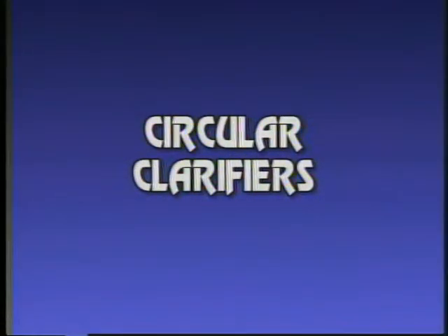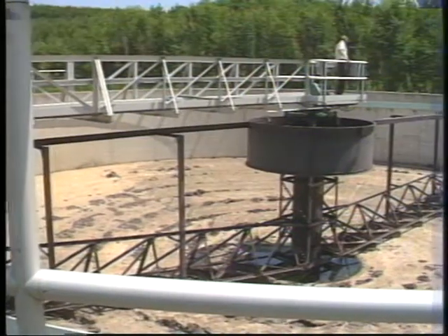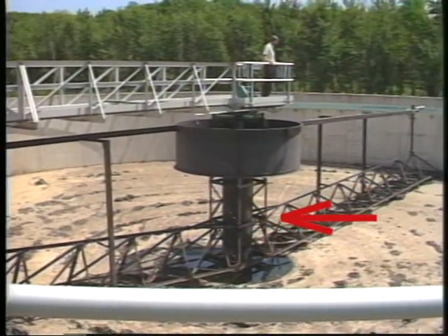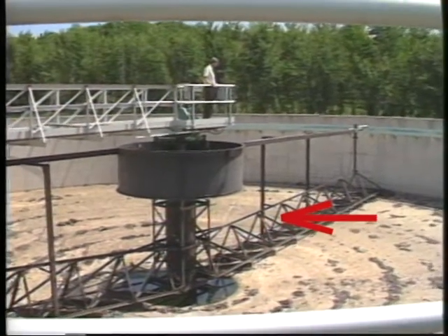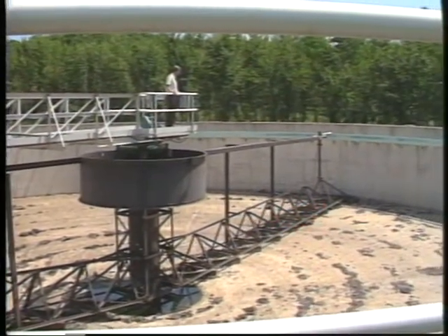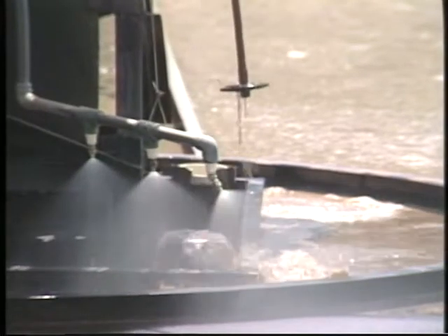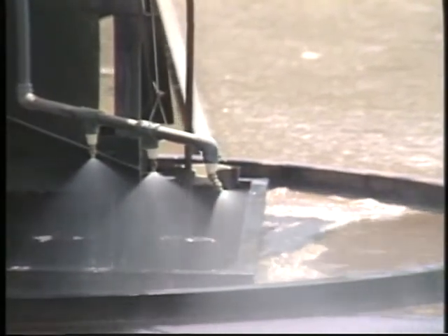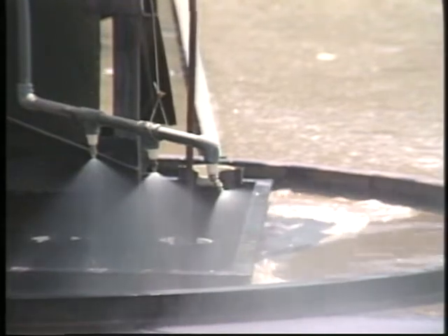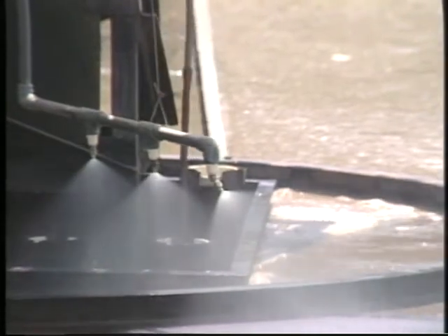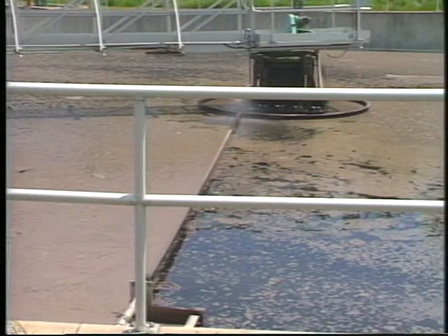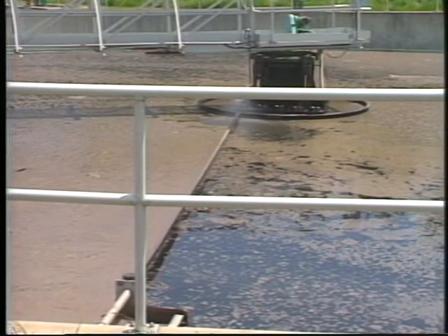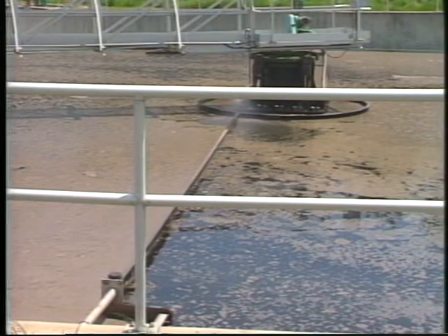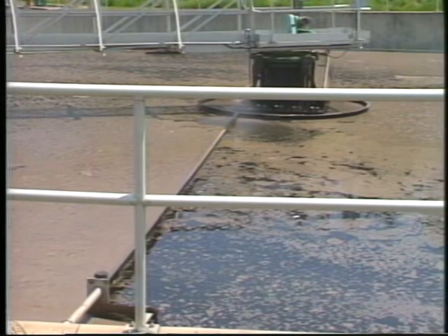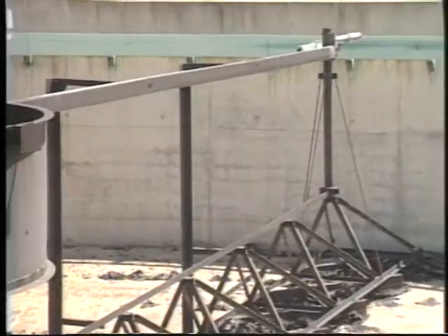Now let's take a closer look at circular clarifier mechanisms. In these units, the wastewater enters through the center column and into the influent well. The influent well is a baffle that slows the velocity of the wastewater and distributes the wastewater evenly throughout the clarifier. As with rectangular clarifiers, the operation of the sludge and scum mechanisms should be observed closely. Circular clarifiers may have a mechanism that consists of blades or scrapers that move the sludge towards a hopper in the center of the clarifier.